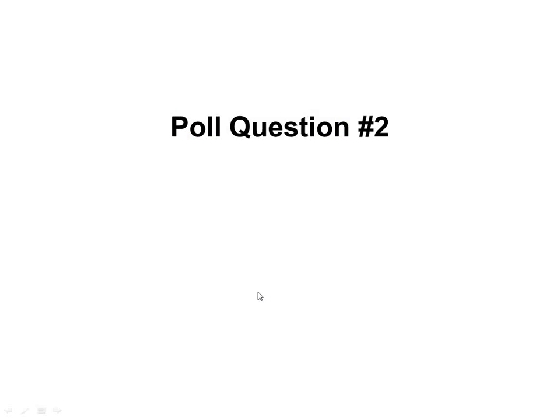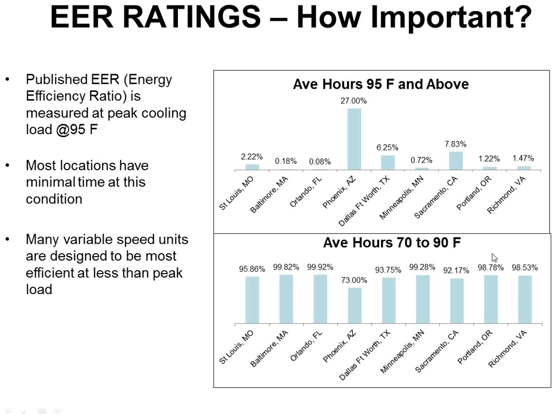Unless you're in Arizona or Las Vegas or something, you're not running that many hours at 95-plus degrees. I didn't put Chicago on here specifically, but if you look at St. Louis, 2% of the hours, Minneapolis, 1% of the hours. So we're somewhere in between there here in Chicago and Northwest Indiana. Very, very few hours on the cooling side are above 95 degrees. The same thing happens on the heating side, which I already talked about. But for cooling, EER is not very exciting. We need to look at things from a part load standpoint. Specifically, once I have variable capacity equipment, whether it's a modulating gas furnace or a variable speed heat pump or air conditioner, as soon as I have modulation, those things really shine when I ramp them down on mild days.